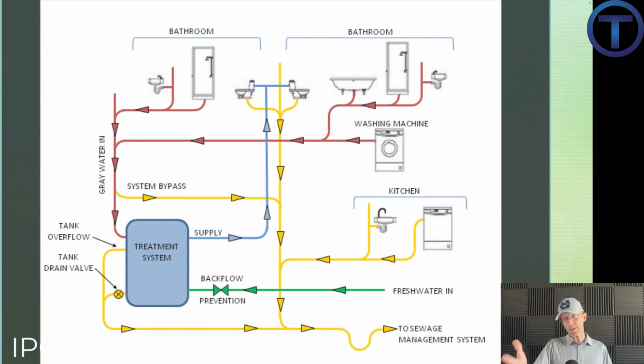Now, I'm going to point something out about all this. This system's pretty cool, right? You've got this coming this way and that going that way, but what you have to observe is the fact that it's going to take more labor and more material. For the drains, you've got a whole separate system taking gray water over to the holding tank, and you have your regular sanitary collecting toilets and kitchen. Usually, you're going to save pipe and materials if you're just connecting fixtures close together where they're at, right? But now we've created a separate system, also requiring separate venting. So now we've got more vents.